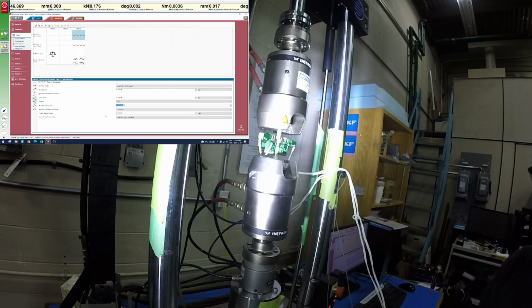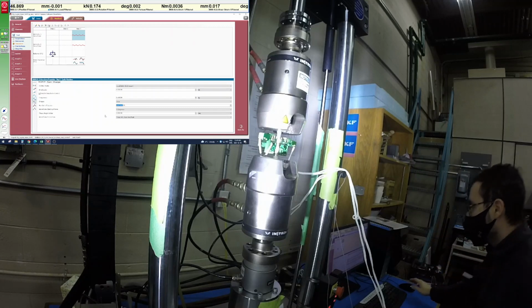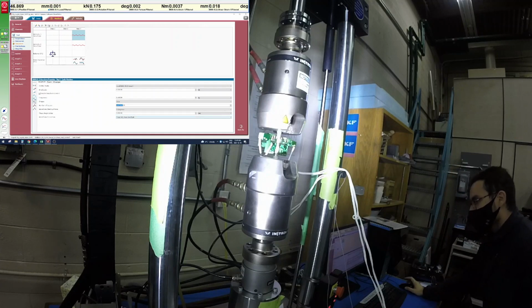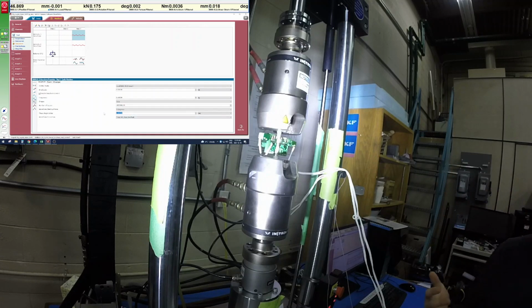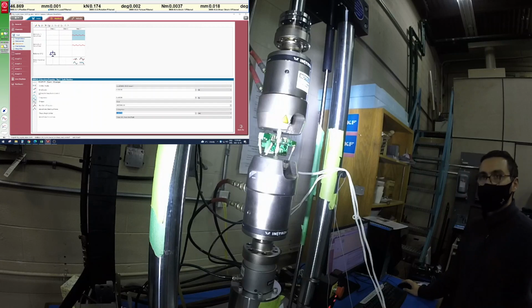If you want to do a non-proportional test with phase offset, you can just input 45 or 90 here for the phase angle delta. It doesn't matter if you do it on the first waveform or the second. Generally, it's the rotational direction that you're going to do it on, but just make sure you don't do both, because the effects of those will be combined. So we'll leave that at 0 because we'll just do an in-phase biaxial test here.